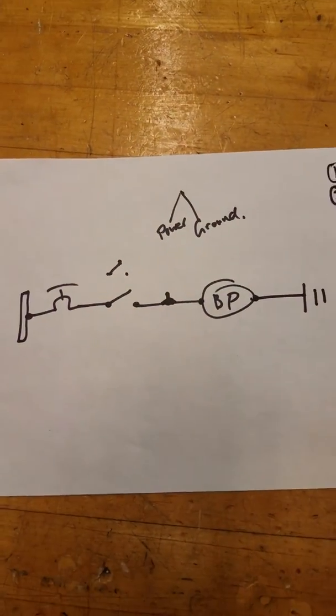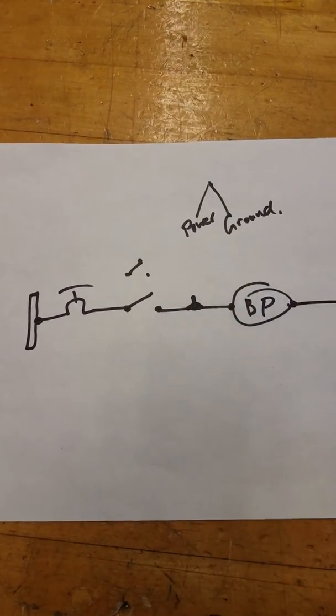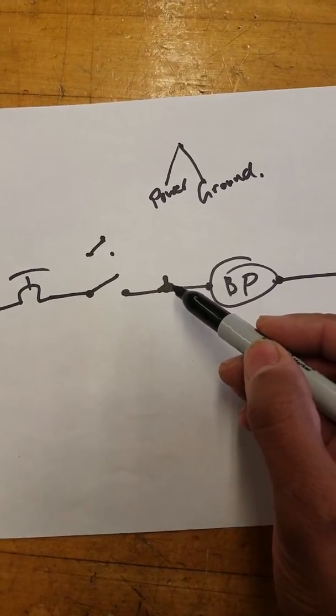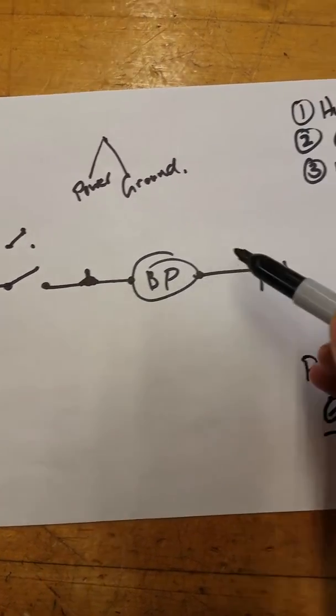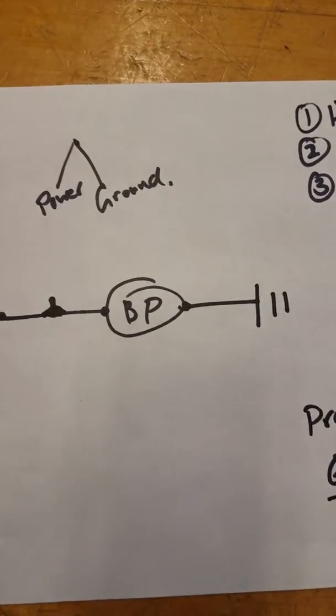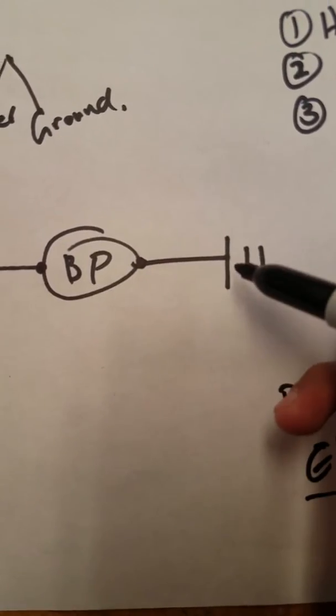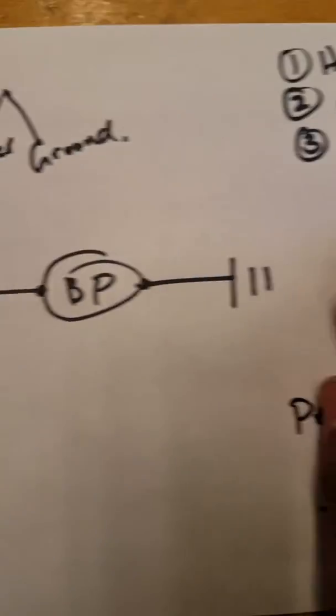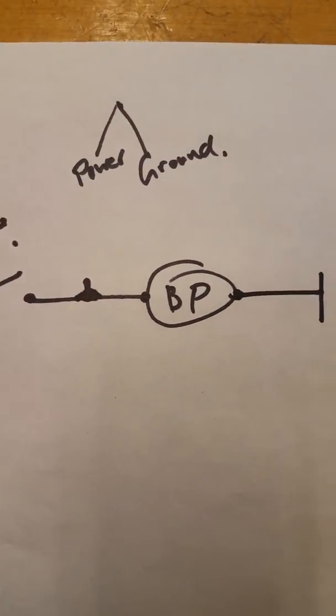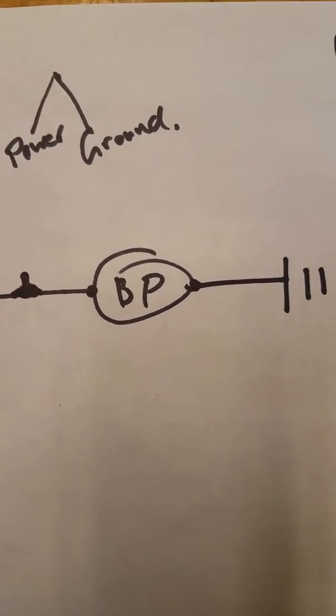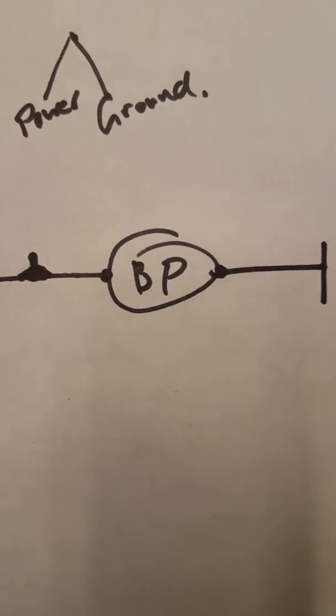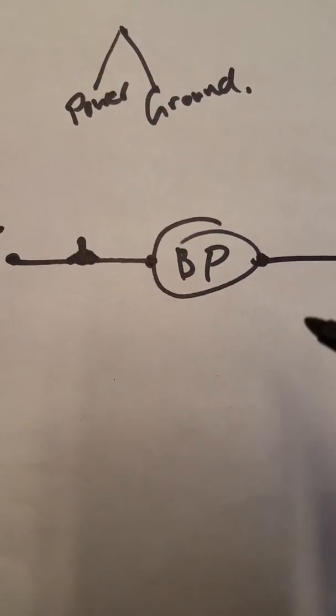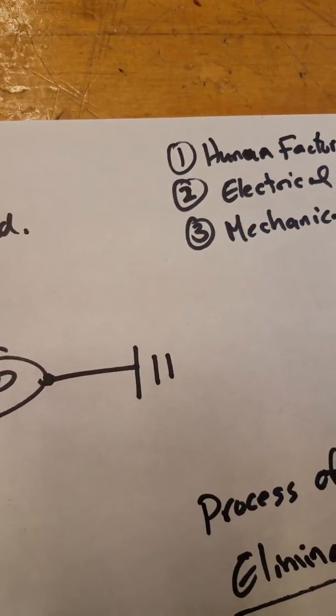Here's a primitive boost pump circuit: there's a bus, a circuit breaker, a single-pole single-throw switch, a terminal post connecting the switch to the actual boost pump, and a ground for the boost pump. If you're missing the ground, the pump will not work on that side. If there's no power coming in, the boost pump will not work either. Neither power nor ground is more important — both are required; without either one the boost pump simply will not work.